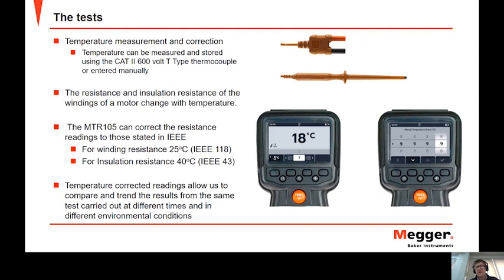The importance of correcting the IR values for temperature is because the temperature affects the IR values greatly. So the rule of thumb is for every 10 degrees Celsius increase in winding temperature, the IR value halves. So if we don't make a correction for temperature, the trending of the IR is impossible, particularly in countries where you get great fluctuations in temperature, summer to winter. So in the UK, we can have 0 degrees C. In summer, if we're lucky, we might have 30 degrees C, and it can be anything in between. So if we're not correcting to 40 degrees C, which is the IEEE 43 standard for correction, then those IR values will be changing greatly, and it's impossible to trend.